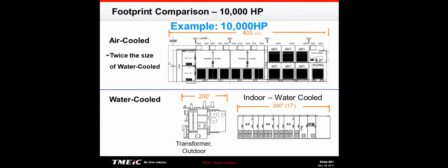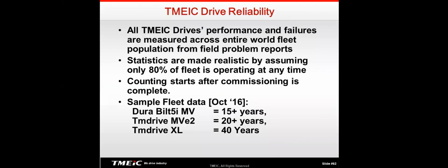Here's an example at 10,000 horsepower of an air-cooled drive versus a water-cooled drive. So you can see the reduction in size. And as you get up into multiple tens of thousands of horsepower, you just really have to go to a water-cooled drive. There's your fleet reliability. Again, they go from 15 to 20 to 40 years mean time between failure.